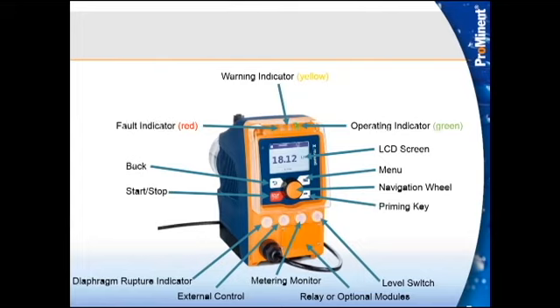As it's counting down on the screen, I can then turn that dial to either increase to keep going with the priming sequence or go down to end the priming sequence. And I'll show you that next week when I have a webcam on the pump to go through that. You hold in the menu button that will get you through the different menus, and you navigate with that navigation wheel that's there.